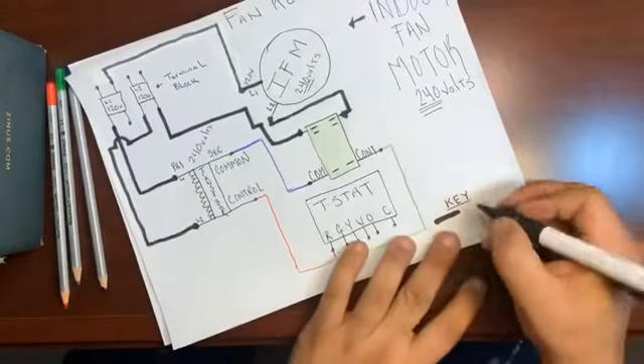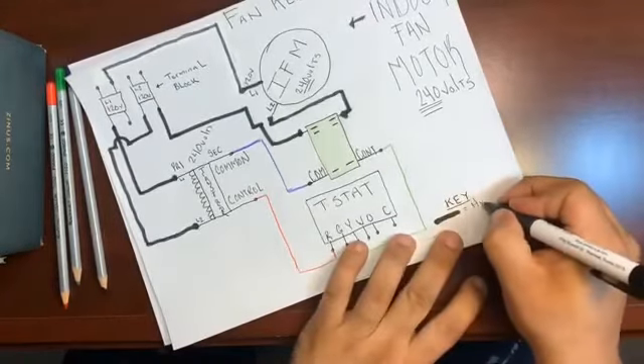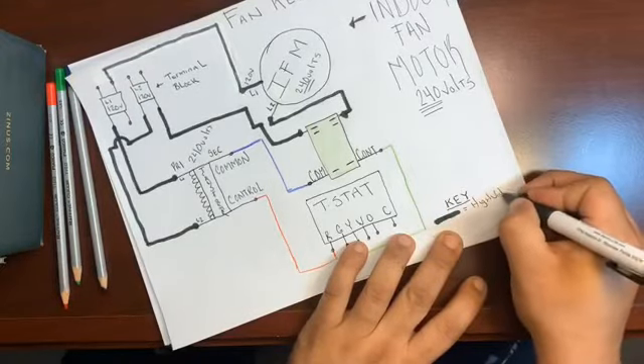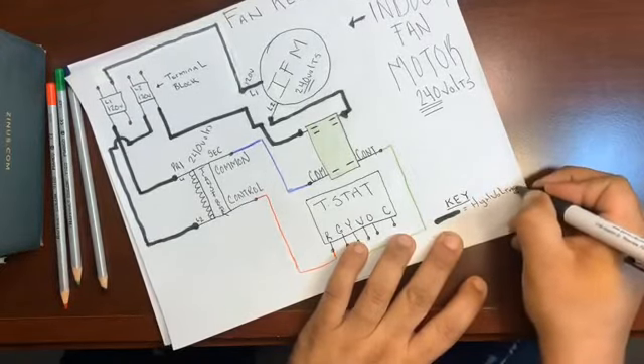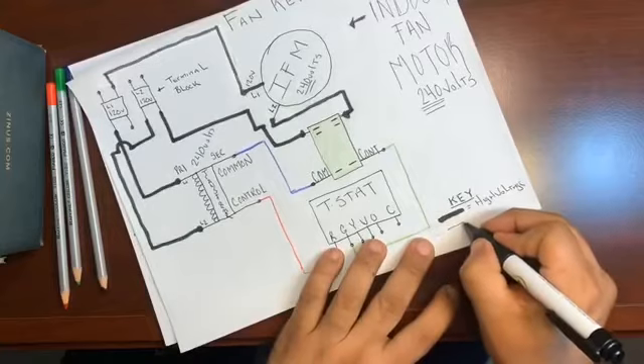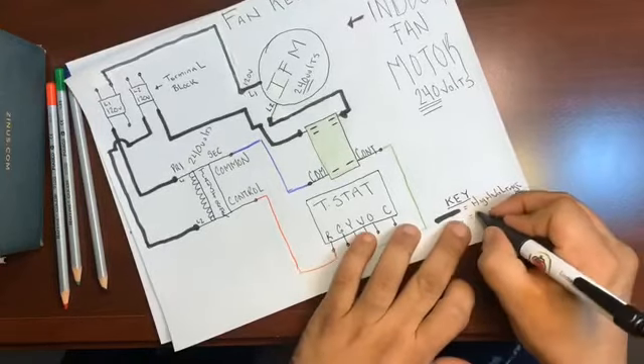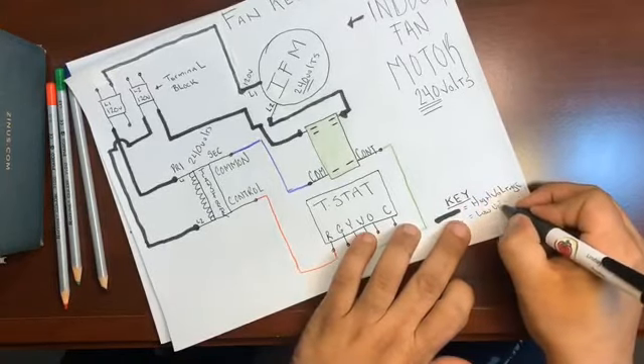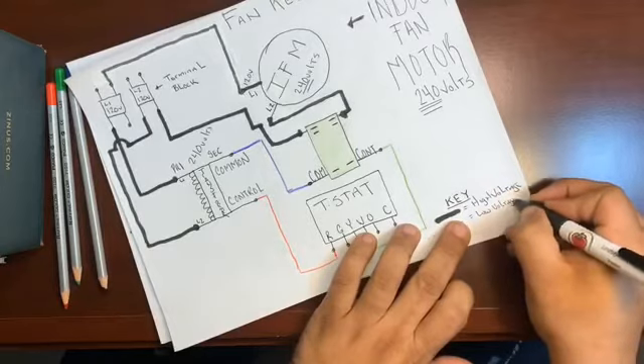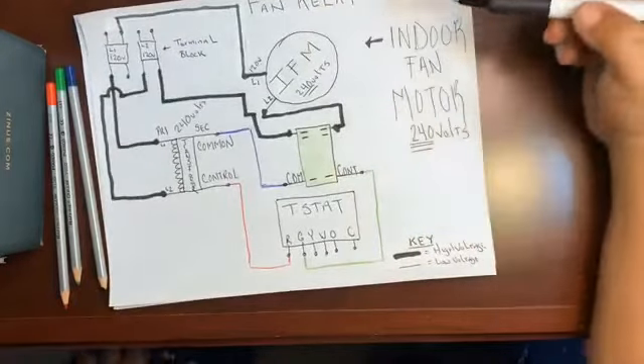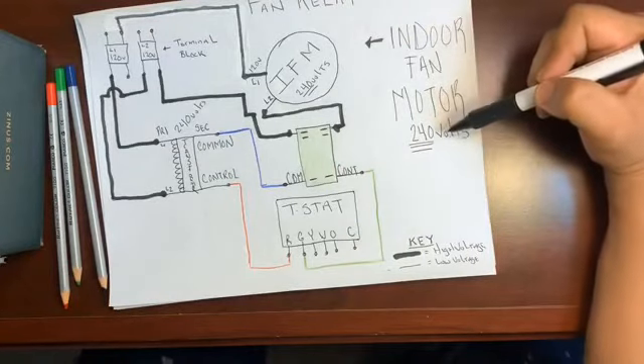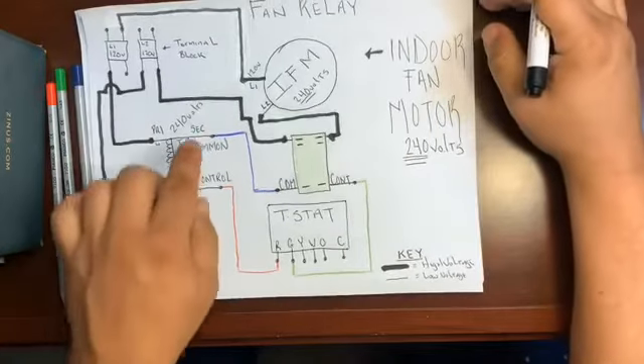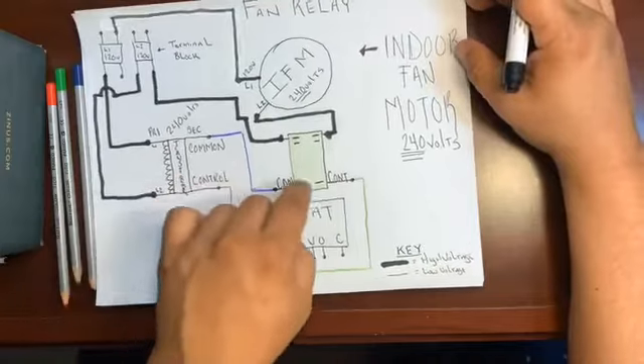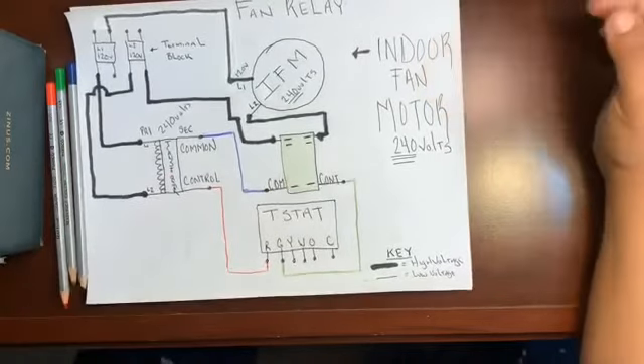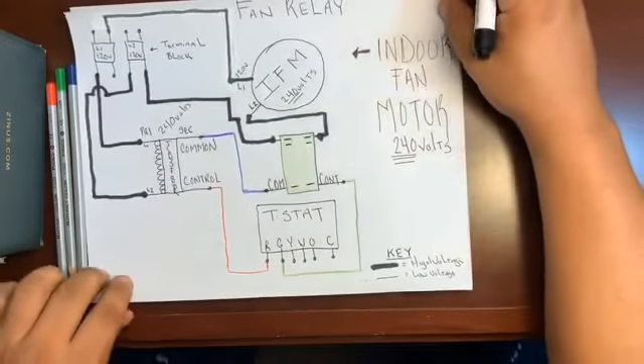Then we can write equals high voltage. And then just a thin line equals low voltage. So this is our fan relay. Our fan relay controls our indoor fan motor of 240 volts. And again, the common on the secondary side controls every single relay. So that's 2 out of 4 relays, halfway there. Let's keep going.